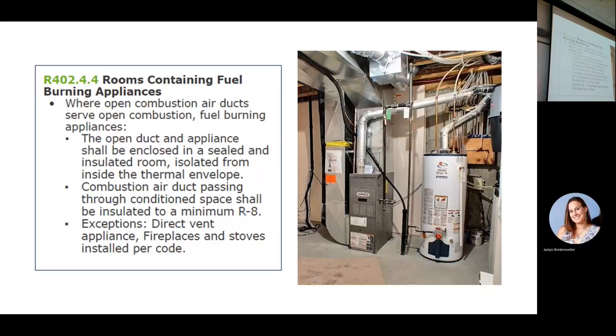And so what the code says, and you can blame me for it and some of my friends from Colorado, because we finally got together and we put it in the code, that if you have this condition with open combustion air ducts serving open combustion fuel burning appliances, the open duct, so the combustion air duct and the appliance or appliances need to be enclosed and sealed in an insulated room, isolated from the rest of the envelope. So it's the same thing as a sealed fireplace with combustion air coming into it. We're creating its own separate environment. We bring the air in, we let it go out, and it doesn't impact the rest of the inside of the house.